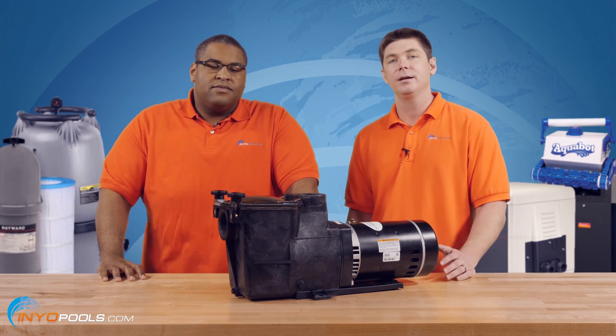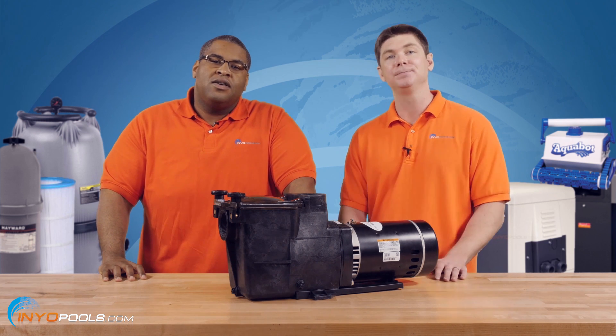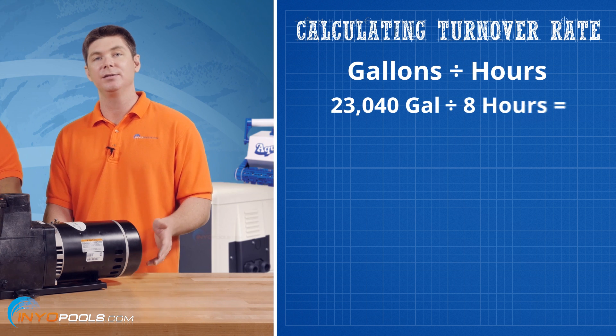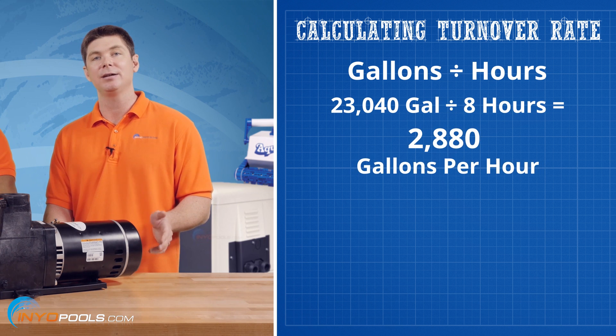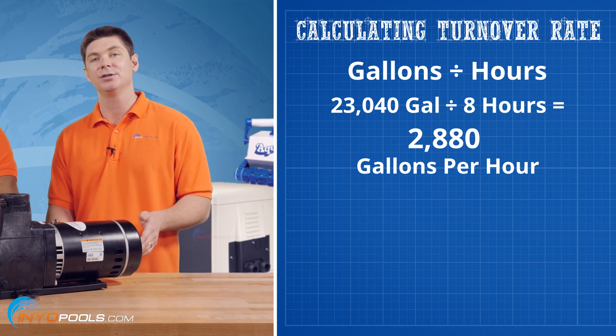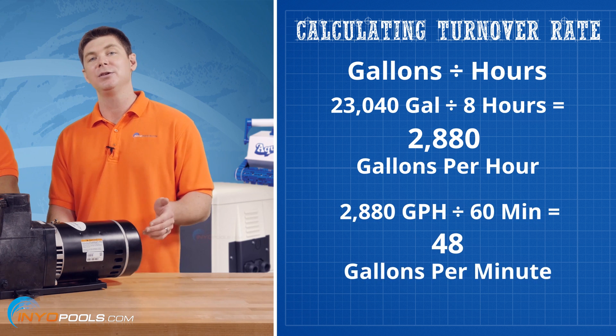The goal of any residential pool is to turn over your body of water once a day. The general rule is 8 to 10 hours — that's the pump run window you want. In this example we'll use 8 hours. Take the gallons and divide by hours to get gallons per hour: 23,040 divided by 8 equals 2,880 gallons per hour. Then divide by 60 to get gallons per minute: 2,880 divided by 60 equals 48 gallons per minute.